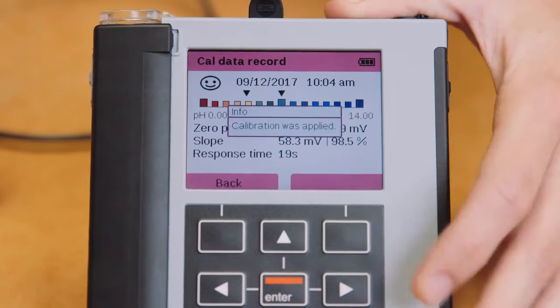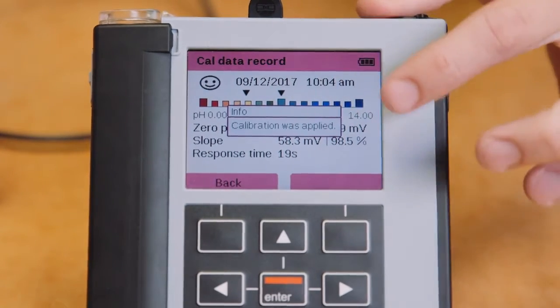We can now press apply, which writes the calibration data to the MemoSense sensor head, or discard to begin the process again. This completes the offline calibration process of our MemoSense pH sensor. As you can see, the entire procedure took less than 2 minutes and was done conveniently right here in our workshop. This sensor can now be stored on the shelf with the rest of our pre-calibrated MemoSense sensors. It's now ready for field exchange at a moment's notice.